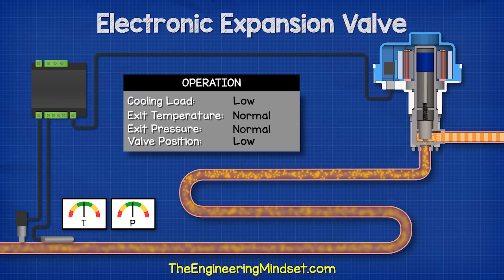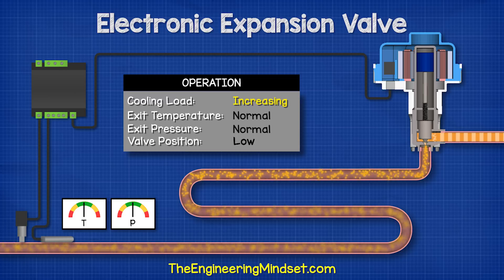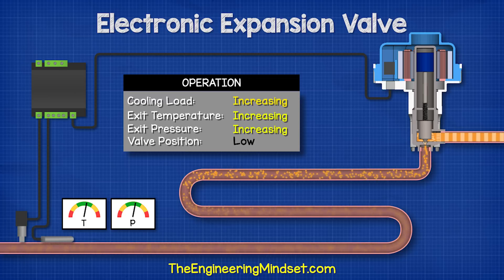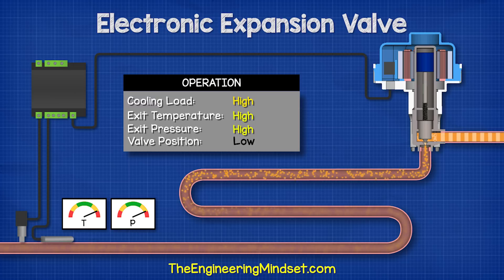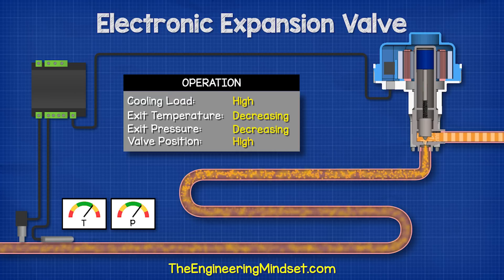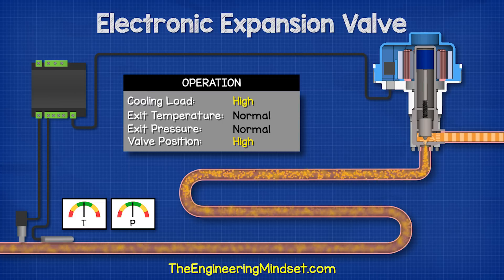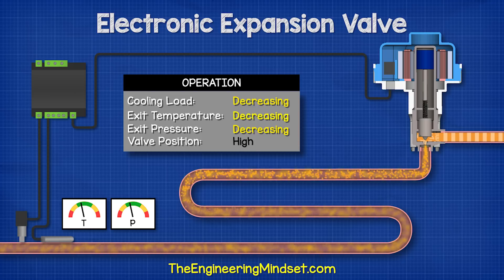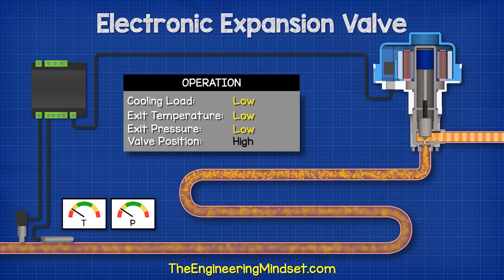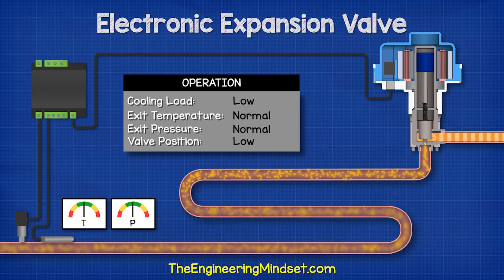When the cooling load on the evaporator suddenly increases, the refrigerant is going to boil much faster. There isn't enough refrigerant currently inside to cover this demand so the suction line temperature and pressure will increase. The sensors detect this and so the controller tells the valve to open further to allow more refrigerant into the evaporator. When the cooling load decreases, the refrigerant will boil more slowly so there will be too much refrigerant inside the evaporator. The temperature and the pressure will therefore decrease, and the controller tells the valve to close further to reduce the amount of refrigerant entering the evaporator and maintain the correct superheat.